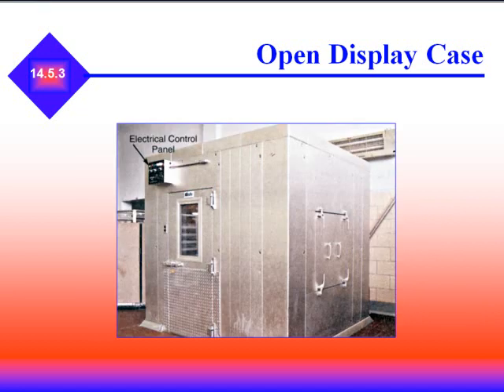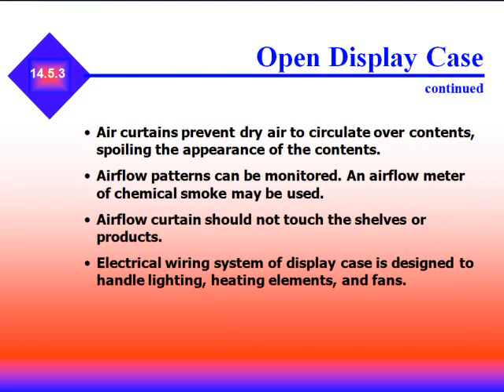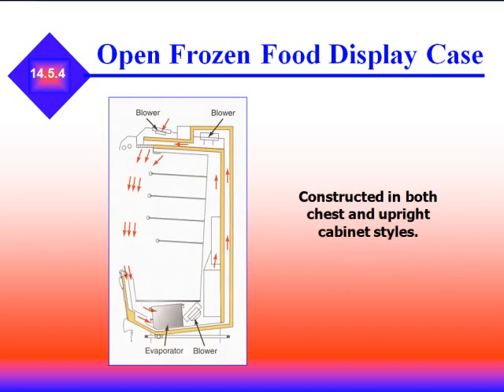This is an example of an open display case, often used in produce and kept at about 40°F at very high humidity. Air curtains prevent dry air from circulating over the contents and spoiling their appearance. Airflow patterns can be monitored using an airflow meter or chemical smoke. Airflow curtains should not touch the shelves or products. The electrical wiring system of display cases is designed to handle lighting, heating elements, and fans. The goal is to maintain the air curtain across the front of the case.